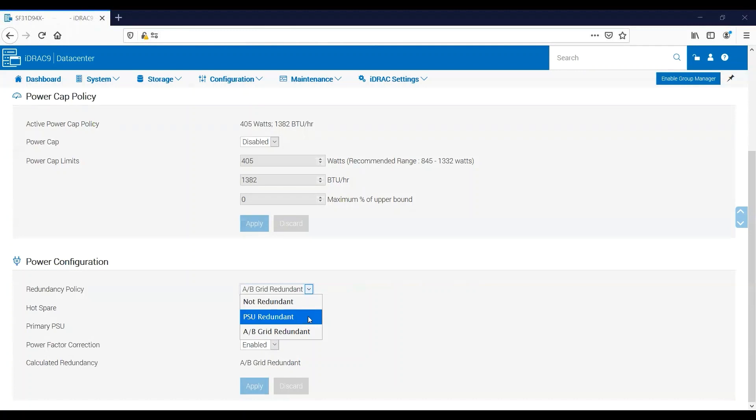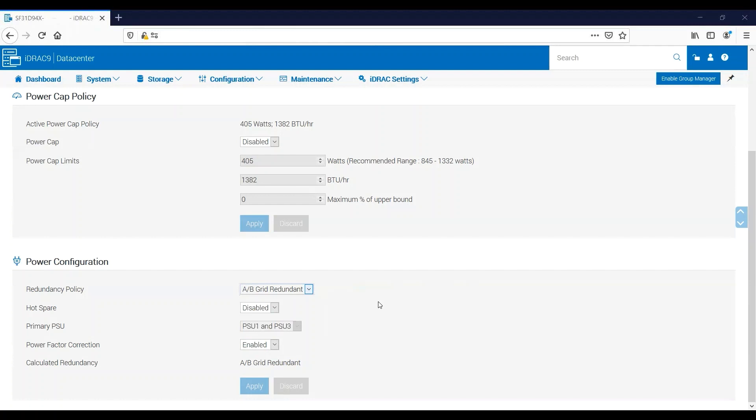The default setting is going to be AB Grid Redundant, and this subdivides your power supplies into two different power grids. Since I have four power supplies, my power grid A is made up of power supply one and three, and power grid B is made up of power supplies two and four. In this scenario, if either power supply in power grid A fails, then we'll fail over to power grid B, and power supplies two and four will take over as the active power supplies.